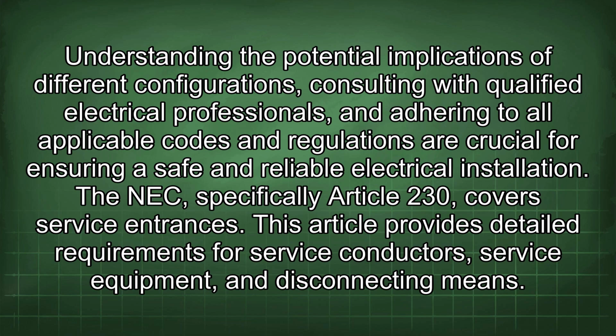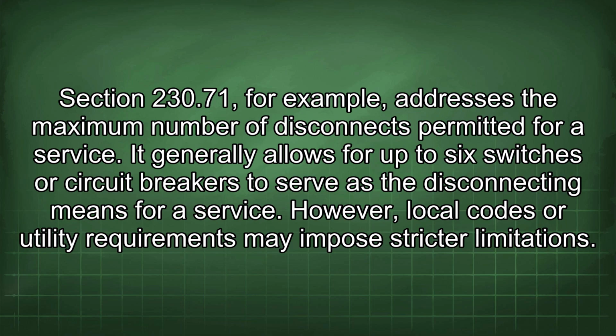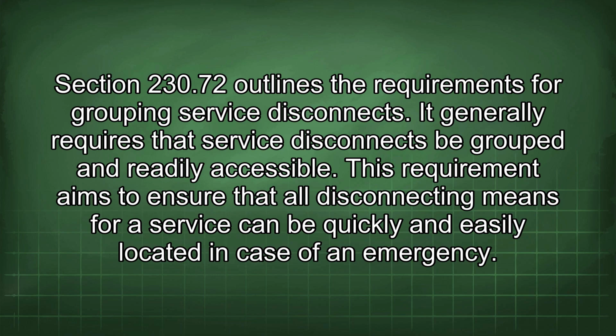The NEC, specifically Article 230, covers service entrances. This article provides detailed requirements for service conductors, service equipment, and disconnecting means. Section 230.71, for example, addresses the maximum number of disconnects permitted for a service. It generally allows for up to 6 switches or circuit breakers to serve as the disconnecting means for a service. However, local codes or utility requirements may impose stricter limitations. Section 230.72 outlines the requirements for grouping service disconnects. It generally requires that service disconnects be grouped and readily accessible.